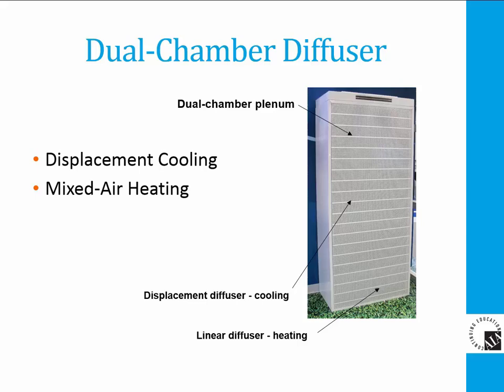Displacement ventilation is generally a cooling-only system. This dual chamber diffuser was designed for a school in Southern California to do heating and cooling through the same ducts and diffuser. It is built with a rear plenum that can supply air to either a large displacement panel for cooling or redirect the air through a lower grill section for heating. The reduced size of the lower grill increases the discharge velocity to get the higher projection needed for heating.